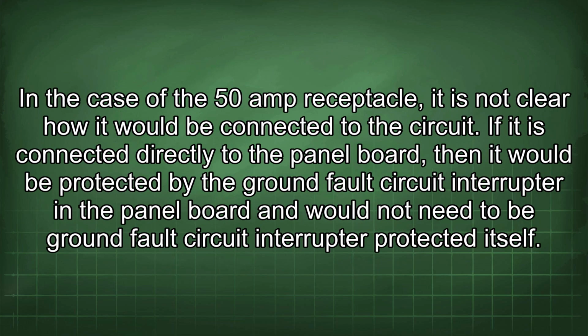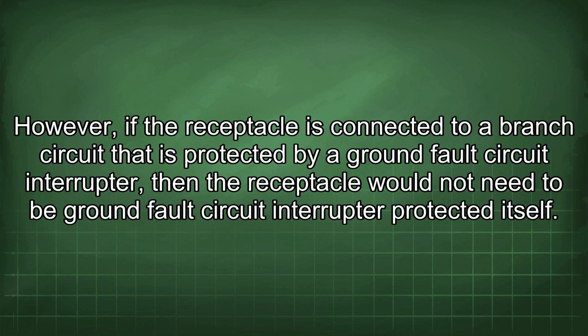In the case of the 50-amp receptacle, it is not clear how it would be connected to the circuit. If it is connected directly to the panel board, then it would be protected by the ground fault circuit interrupter in the panel board and would not need to be ground fault circuit interrupter protected itself. However, if the receptacle is connected to a branch circuit that is protected by a ground fault circuit interrupter, then the receptacle would not need to be ground fault circuit interrupter protected itself.